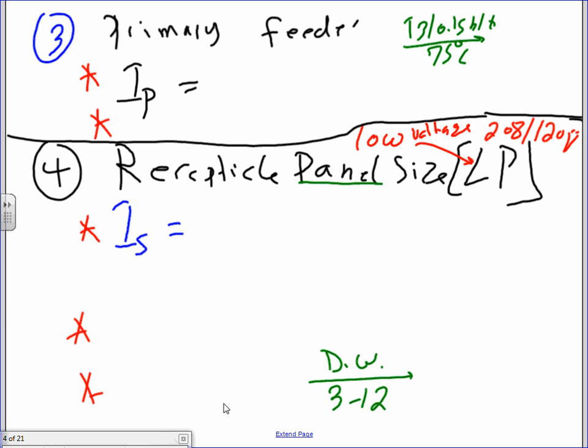The second thing, Adam, to bring the power from the high voltage panel to the transformer, you need a feeder. We don't bring it in a water pipe, we bring it in a feeder, right? To size the feeder, we use the same approach as the primary overcurrent device. I primary is 36.1 amps, which we already calculated. You multiply by 1.25. We're assuming that over the life of that transformer there could be a continuous load on this feeder. That's an assumption, and it's a good assumption. If you do the math on 36.1, that gets you 45.1 amps.